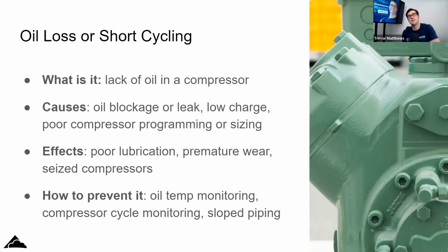Oh, there's a high percentage of oil failures. And once again, this is something that a lot of technicians don't dive into because it's unknown. I can't see it. It makes them uncomfortable, outside the comfort zone. They're not confident on it. But oil loss, oil failures is another big failure, but it's usually caused by something else. Like you could have floodback that washes out the oil. Like you're saying, short cycling: the compressor turns on for a second, shuts off, turns on, and it just keeps having a higher pump out rate. It pumps out oil all the time.